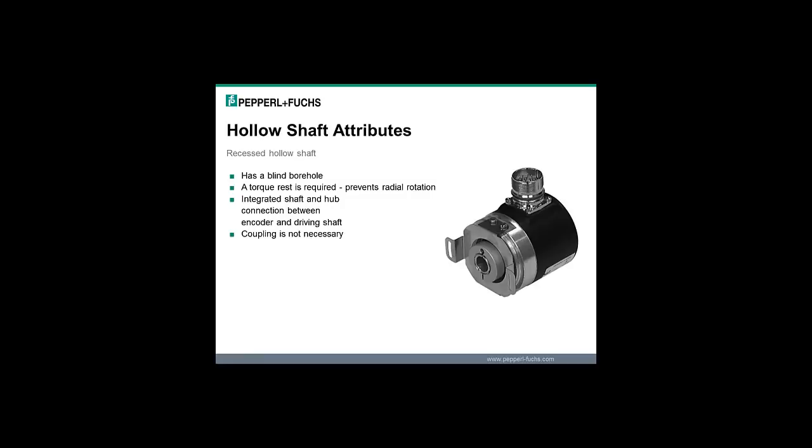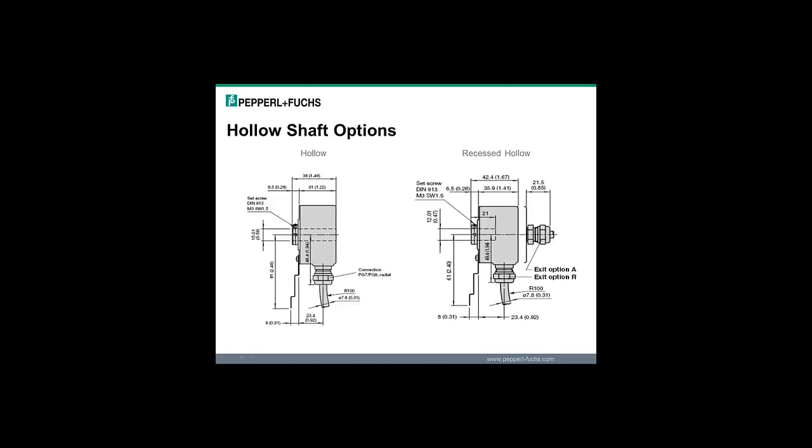The recessed hollow shaft encoder has a blind bore hole that does not go completely through the encoder. There would be a finite depth to this bore hole. This drawing shows a hollow shaft and recessed hollow shaft. The hollow shaft shows a hole through the encoder and the recessed hollow shaft shows a blind hole depth of 21 millimeters. The recessed hollow shaft will have the option of radial or axial cable exit and the hollow shaft will have only a radial cable exit option.